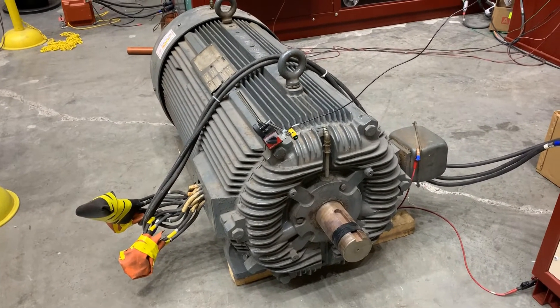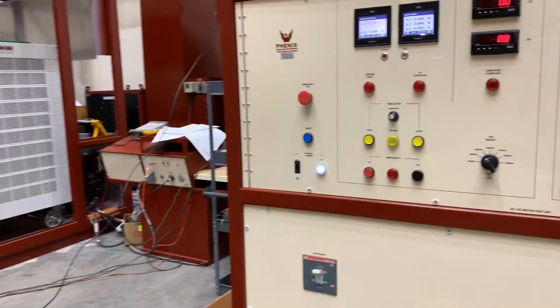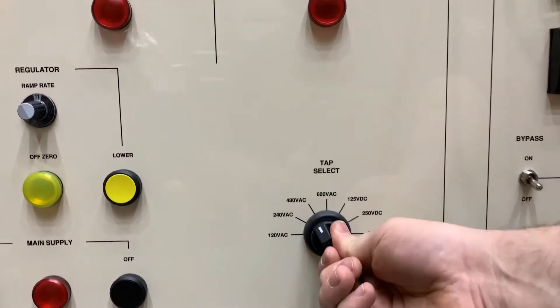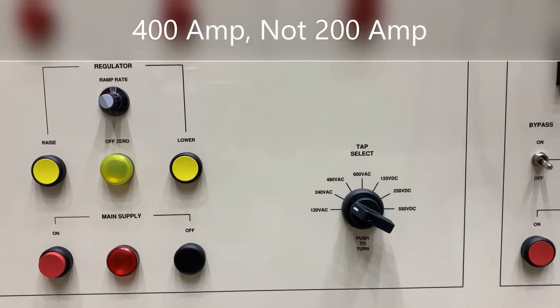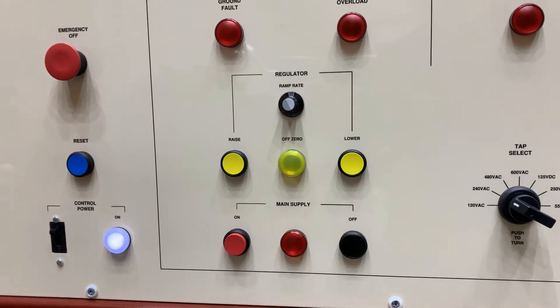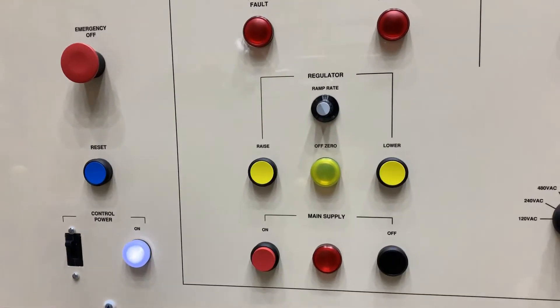We'll go ahead now and run this 500 horsepower motor. To start, we will select the 240 volt tap which has a 400 amp range. This unit can be run up to 200% for a one minute period for breakover.